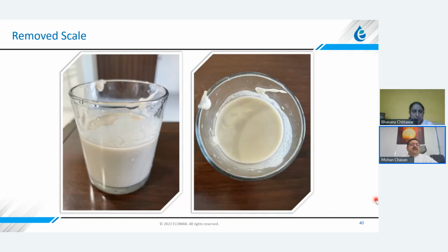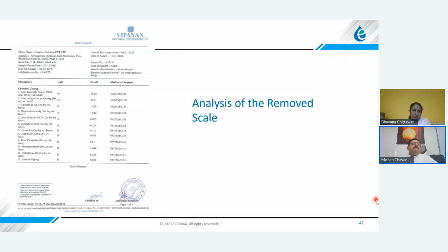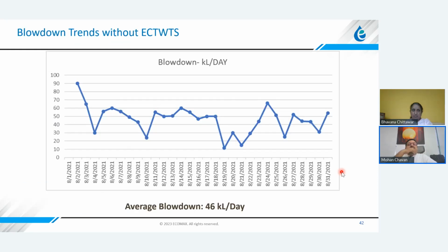This is the scale that is removed from the water. This is how it looks. Because it's automatically cleaned, we need to collect this for sampling and checking it for analysis. So this is the analysis that we did for various elements in the scale. You can see here, calcium is there, magnesium is there, silica is there, sulfate is there, iron is there, orthophosphates are there. That means all these elements are removed from the water, and that's how the water quality has improved. Plus, there is a substantial blowdown reduction. In this particular case, the blowdown was almost 46 cubic meters per day before implementing electrolysis technology.